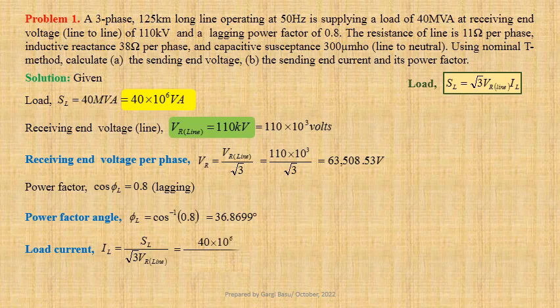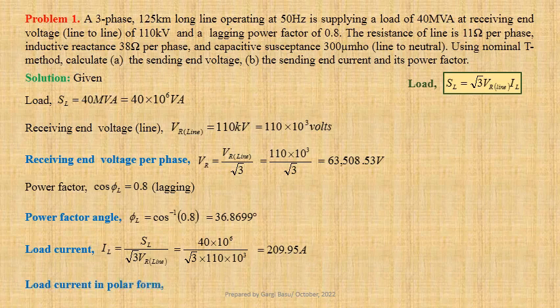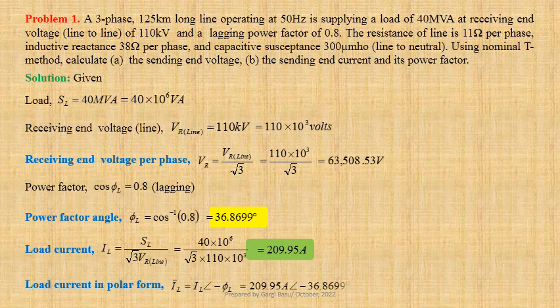The load current IL equals 40×10⁶ divided by root 3 into 110×10³, which gives us 209.95 ampere. The load current may be written in polar form as IL at an angle minus φL, that is equal to 209.95 ampere at an angle minus 36.8699 degrees.